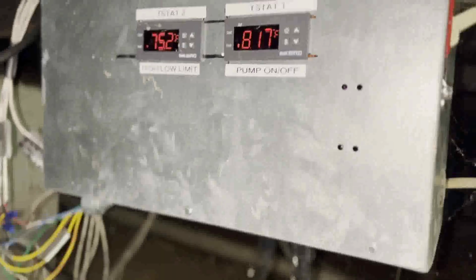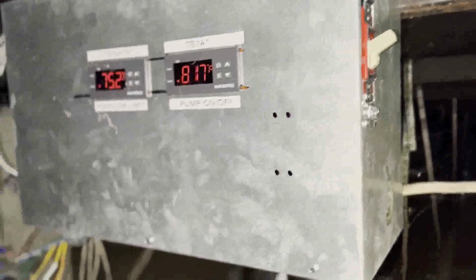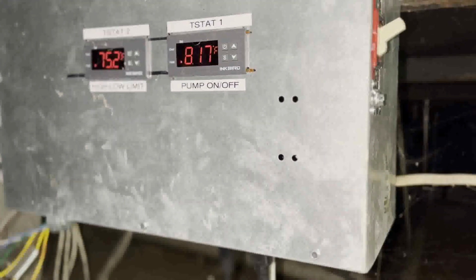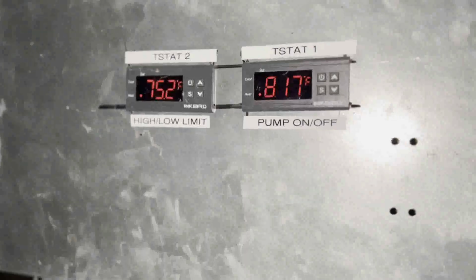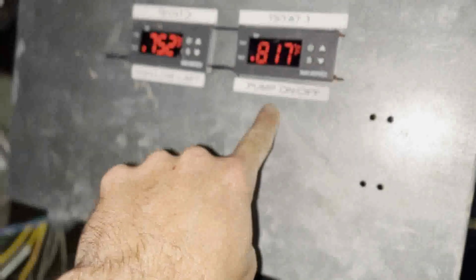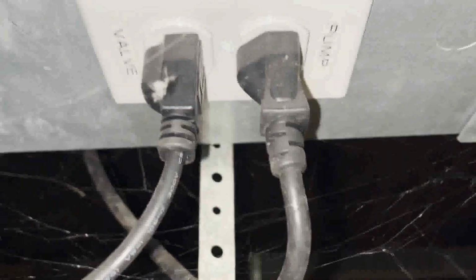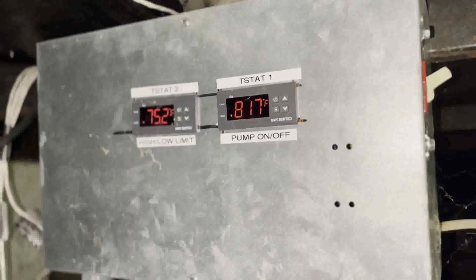All right, we are up under my house. Excuse the mess. I told my kids to clean it up down here, but no one is listening. All right, so what do we have? This is our main controller made out of just some sheet metal, and there's a 120-volt switch. That's a disconnect. Basically, I have two thermostats. This one is pump on, pump off. This one is a high-low limit. There's an outlet under here. One says valve and one says pump. That outlet is broken and separated, so both sides are not hot at the same time. I've got some low voltage wiring there. We'll talk about that in the next video.